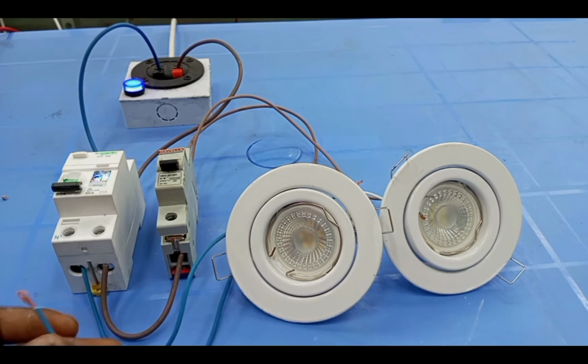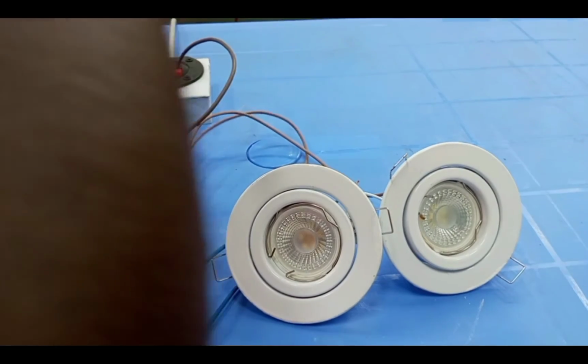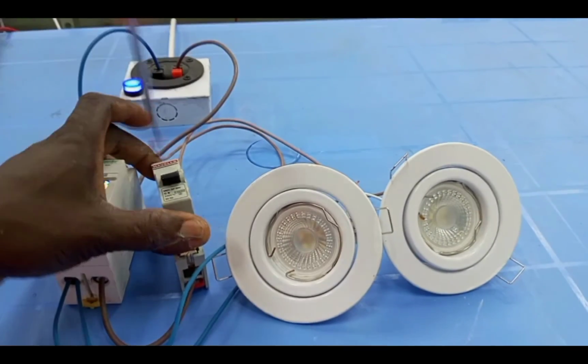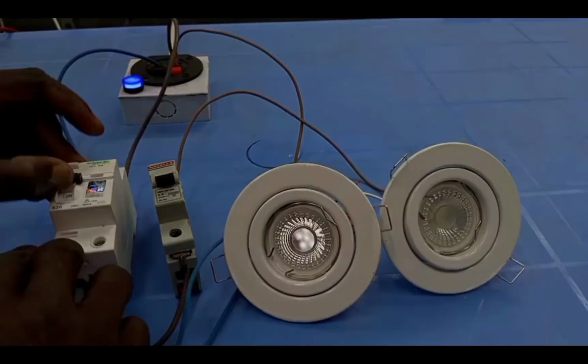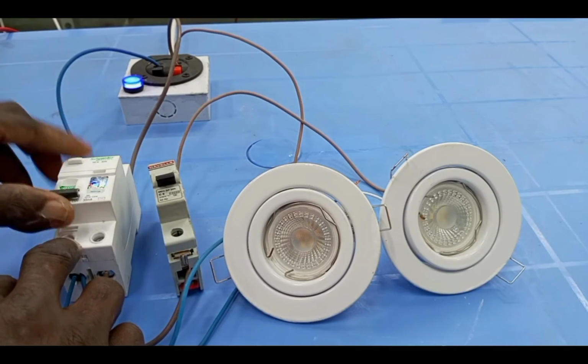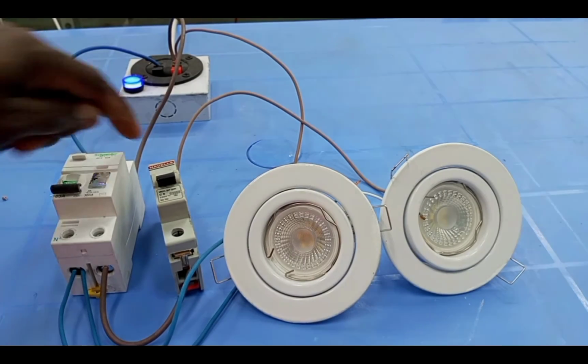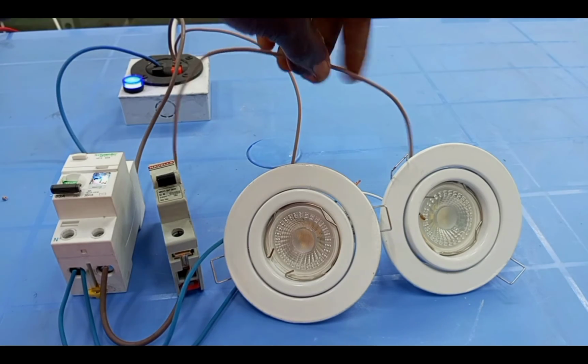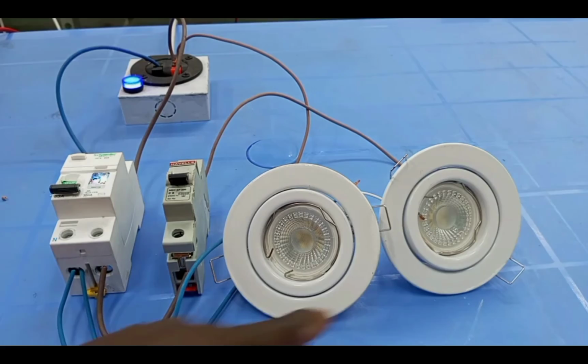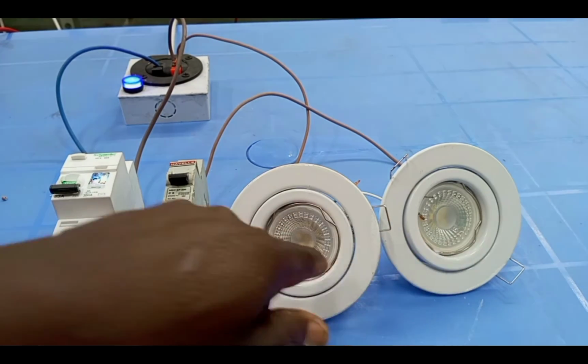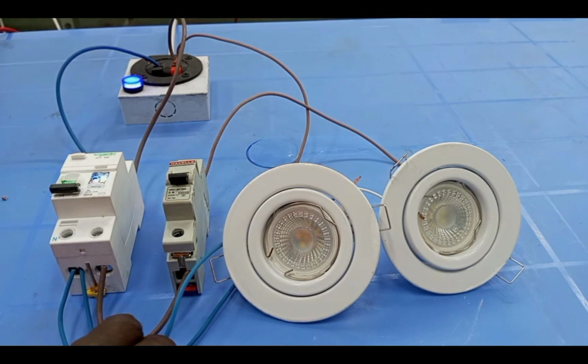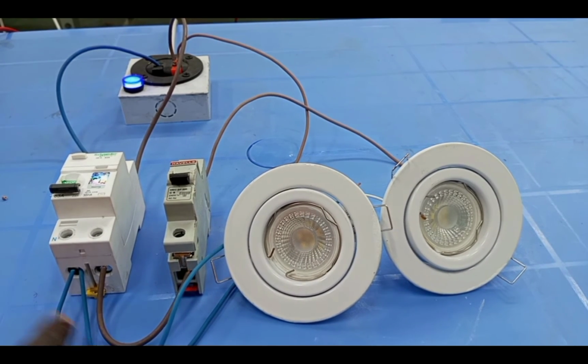The same way, if you connect all the neutral wires from the output of the RCD, but you take the live from anywhere else that is not passing through the same RCD, still it will not work. So let me connect this live wire here, and then let's try to switch it on again. You see, because 0.02 is flowing through the live wire to just one lamp, but when it's coming back, the lamps are now two, and the two lamps are taking 0.04 amps. So it's 0.04 amps that will return through the neutral.